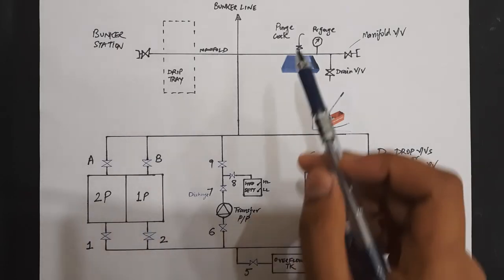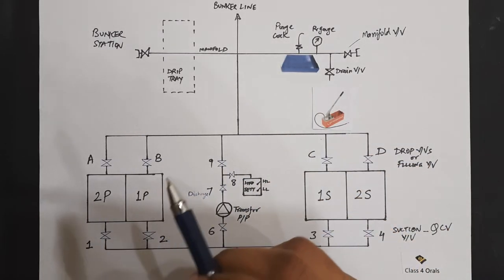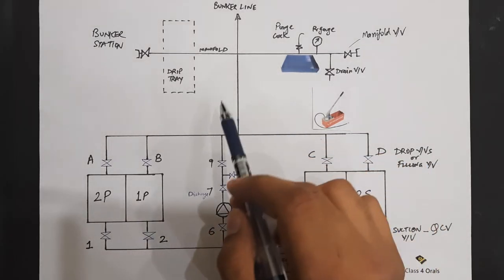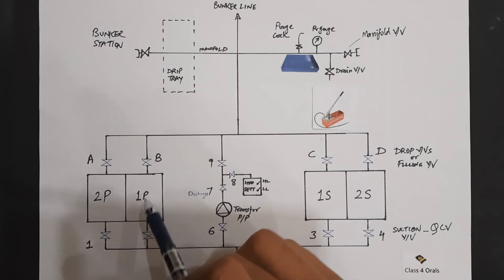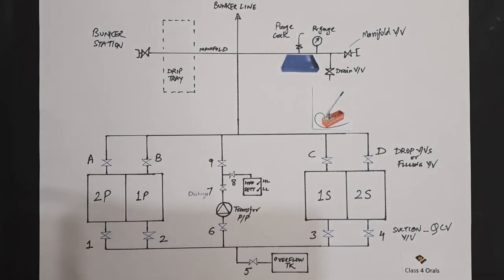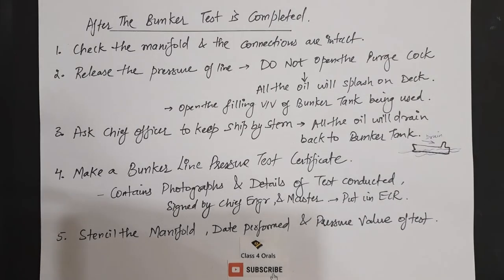What it is going to do? As soon as you open the valve number B, all the pressurized oil will make its way to the one port tank. And this is how we are going to release the pressure from the system. And never open the purge cock. After sufficient level has been drained, you are good to open the purge cock and release the air from there. But always open the number B valve. It will drain all the oil back to the one port tank.